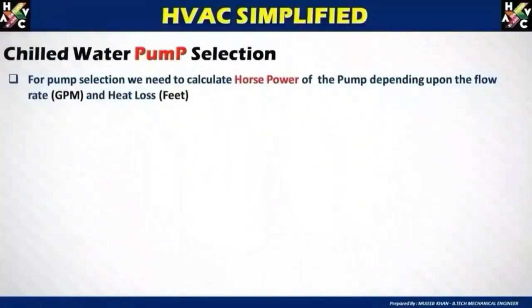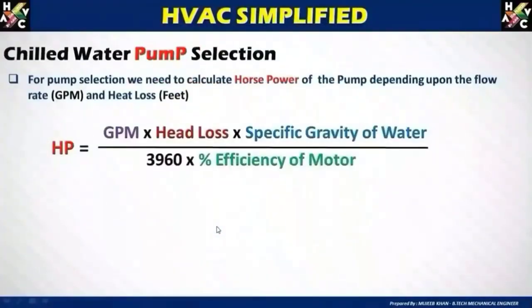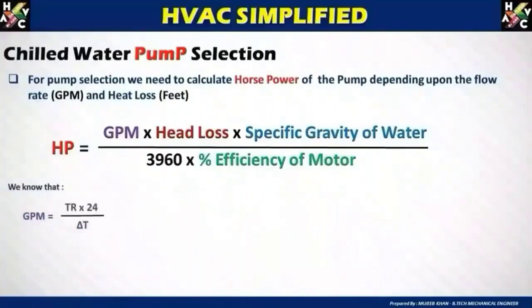For pump selection, we need to calculate the horsepower of the pump depending on two parameters: flow rate in GPM and head loss. To calculate the horsepower, you need GPM — the flow of water — and the head loss in feet, meters, or KPa depending on how you are calculating. The formula for HP (horsepower) is: GPM × head loss × specific gravity of water, divided by 3960 (which is a constant) × percentage efficiency of the motor.